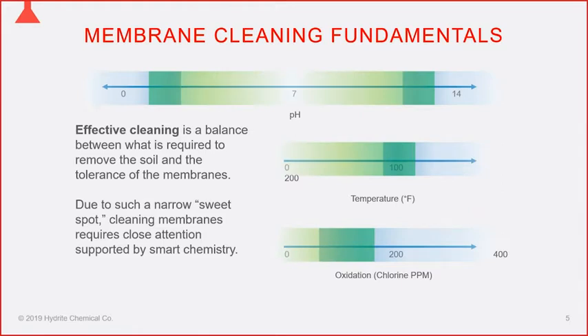For an acid wash, the pH range is 1.8 to 2.2; for an alkaline wash, it's between 10.8 and 11.2. We need to make sure we're not cleaning too cold or too hot, because too high a temperature can damage the membranes, and too cold a temperature results in ineffective cleaning.